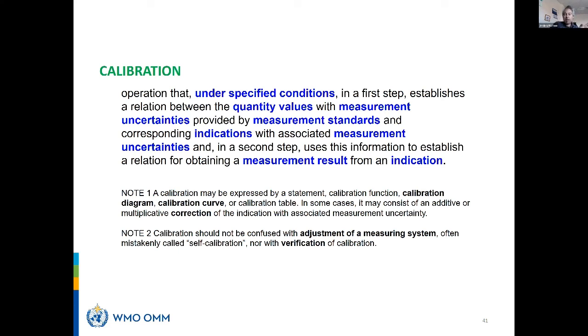At the first step, it sets a relationship between the quantity value with the measurement uncertainty provided by the standard. Who gives you the true value? The reference value is the standard which you bring with you, which you use in your lab. And the relation is with the indication of the instrument that you want to calibrate. Then, when you got this relationship, in the second step, you use it to establish a relationship with the measurement result. It means I have the instrument calibrated. Now I have a calibration curve. This is the second step. For my measurement, I use the reading of the instrument, I adopt the calibration curve, and I get the traceable results corrected by the calibration procedure.